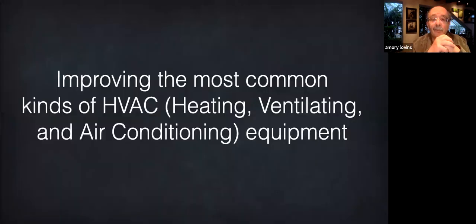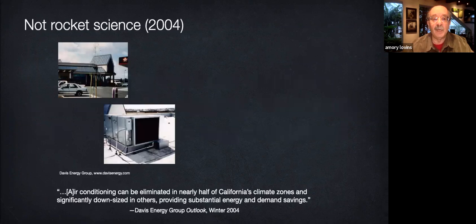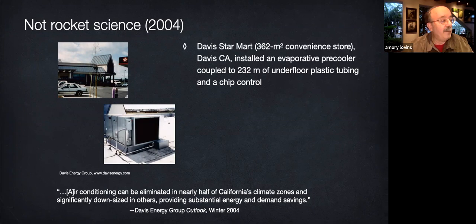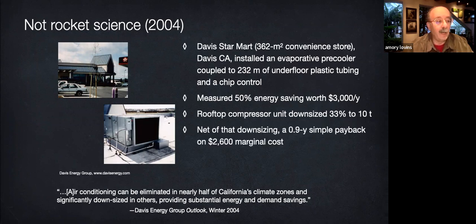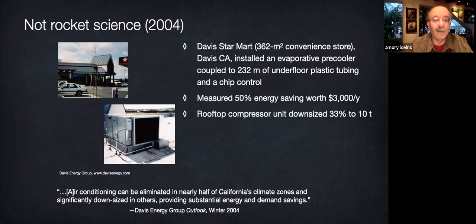Now let's take a few minutes to tour some of the several-fold efficiency gains available in today's common packaged HVAC equipment. It's simple to save a lot of energy in the often dreadful equipment widely used to condition commercial buildings, especially the so-called rooftop units, the big boxes that condition over half of US commercial floor space. In a typical convenience store retrofit in hot Davis, California, 50% energy savings paid back in less than a year from adding an evaporative pre-cooler, a controller, and a little plastic tubing. The compressor shrank by a third, great economics.